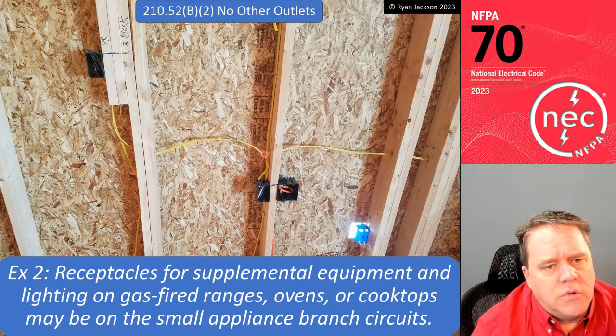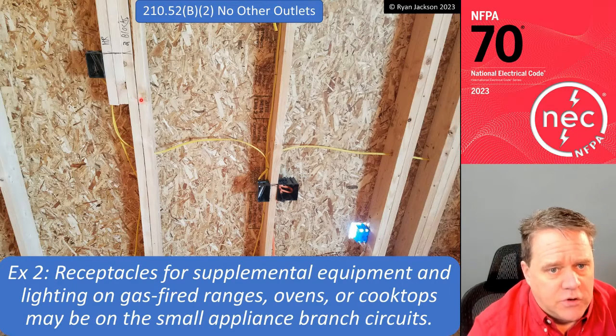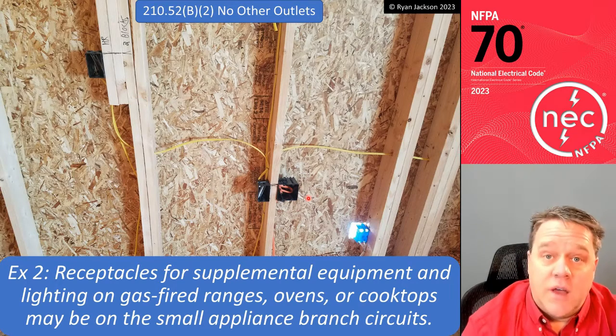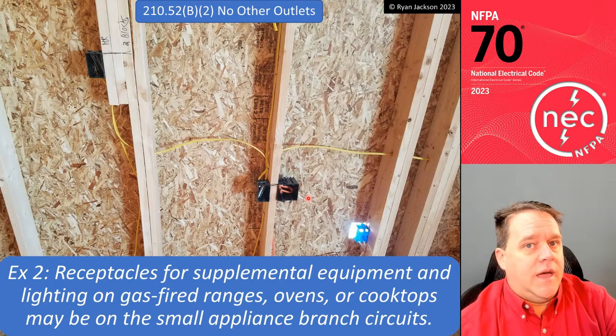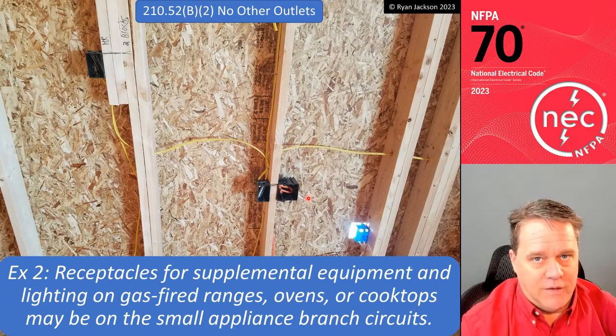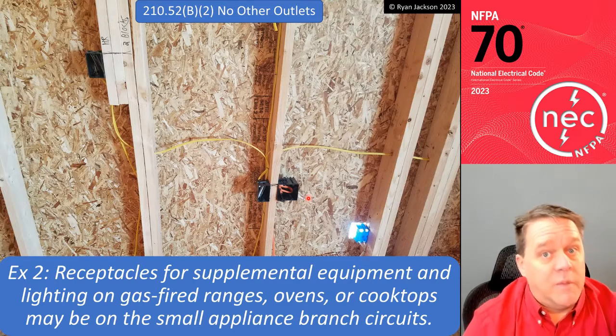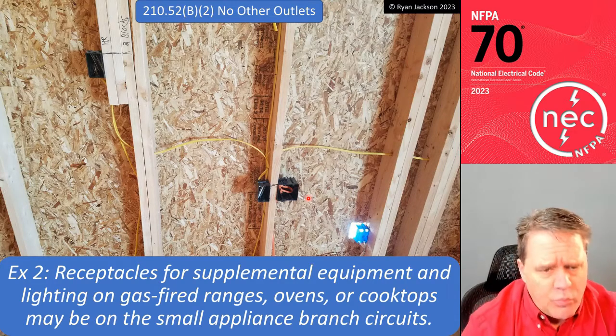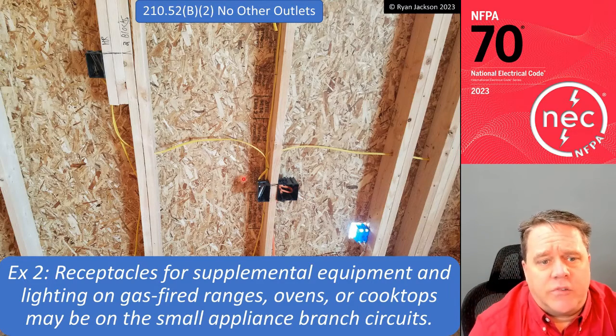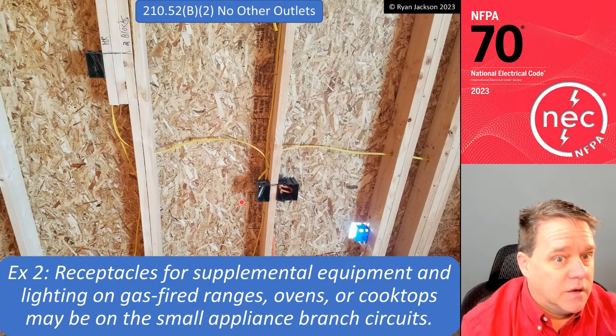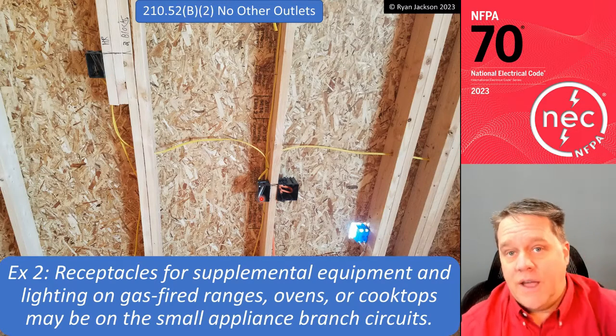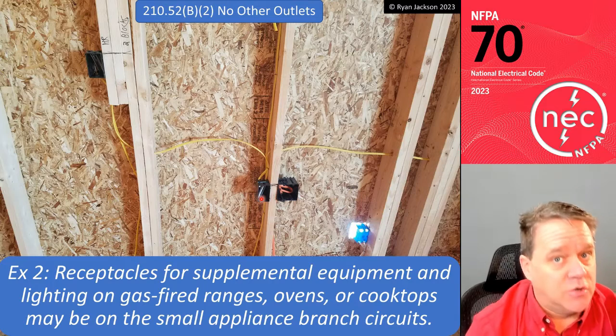You can use the 20 amp branch circuit to pick up the gas igniter. What you cannot have is the microwave on this circuit. And also, where people would screw up, what I would see is they would not put the gas igniter on the small appliance branch circuit, even though you can. They would put it on the same circuit as the microwave, and that's usually a violation.